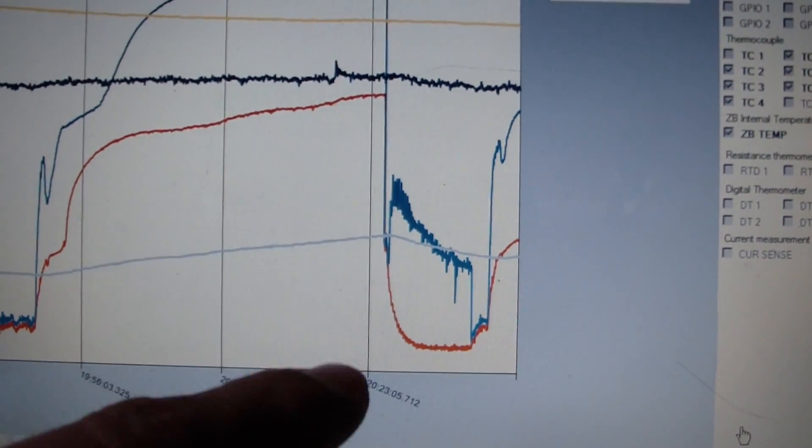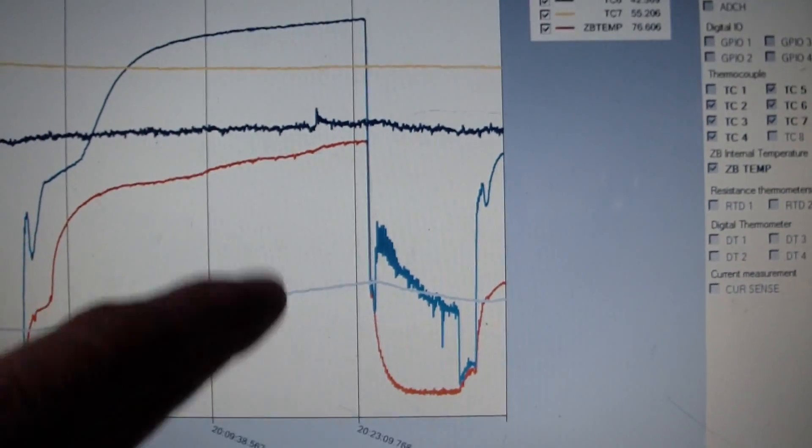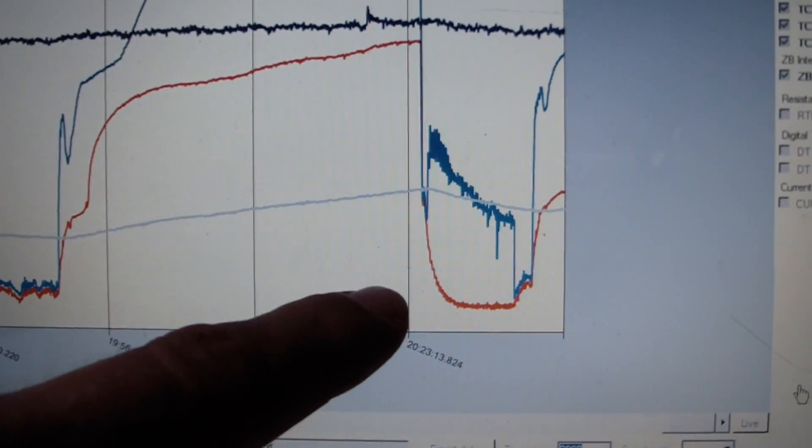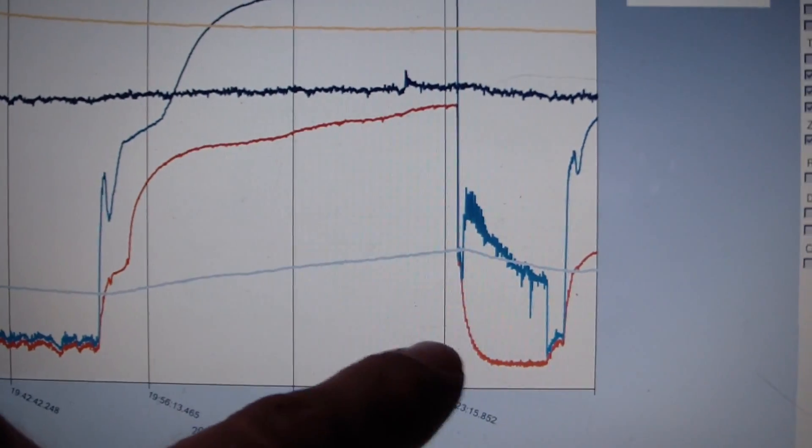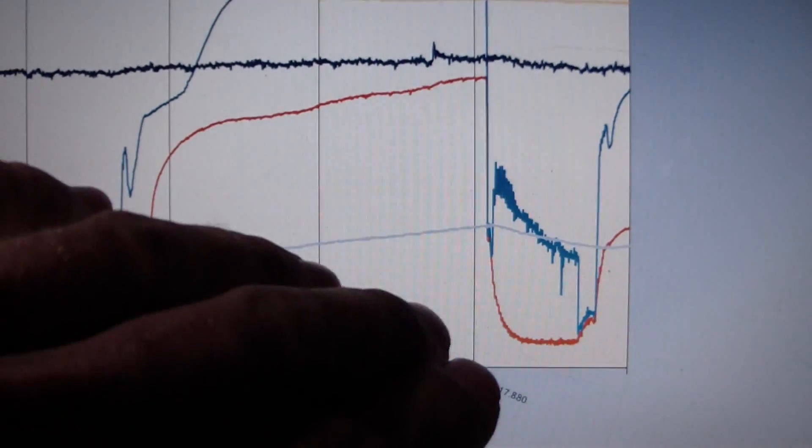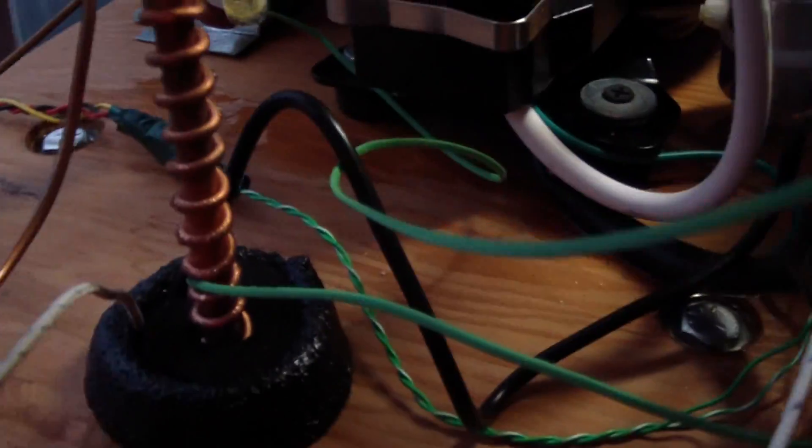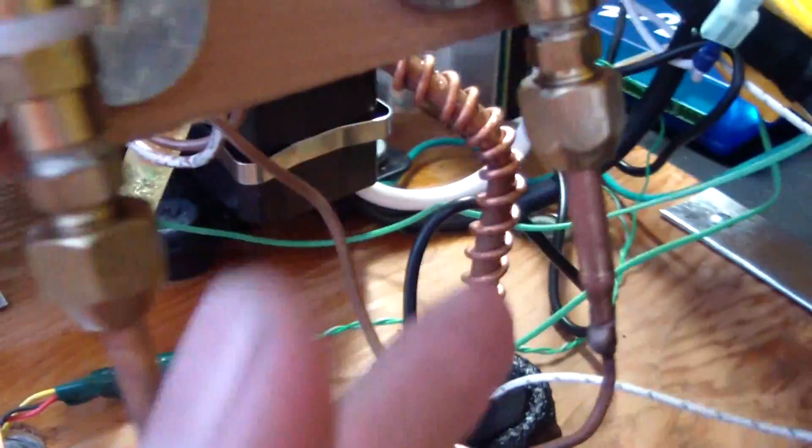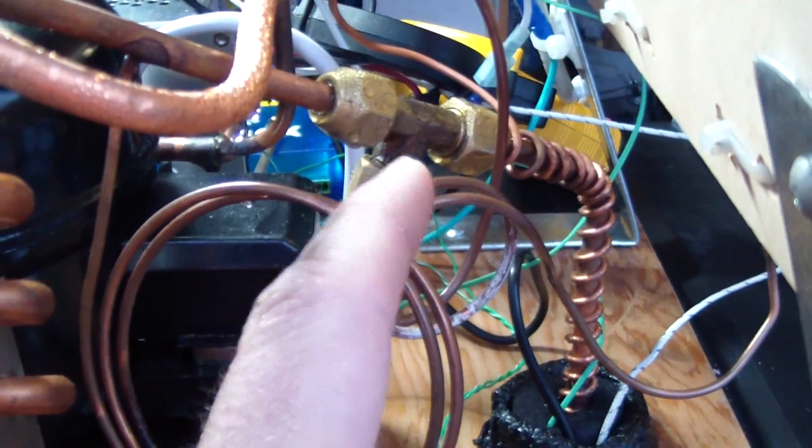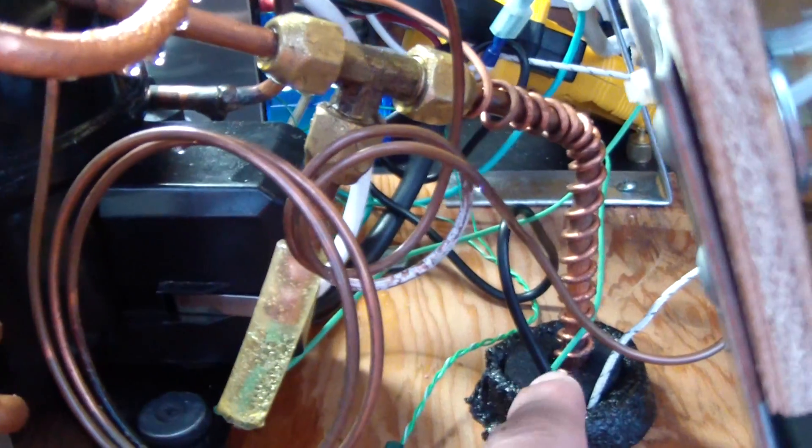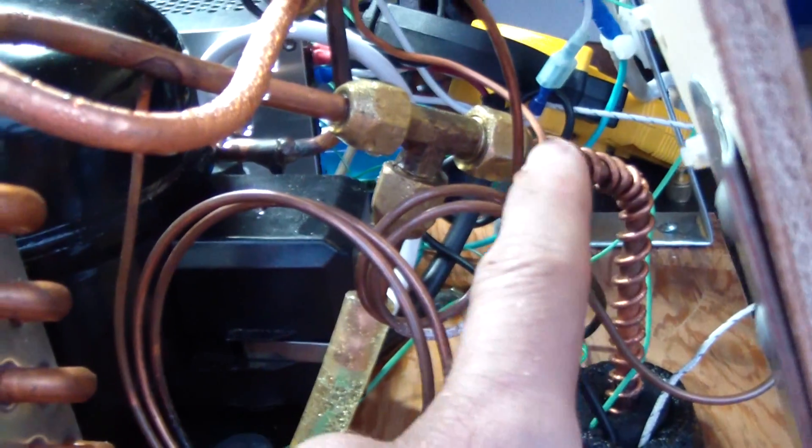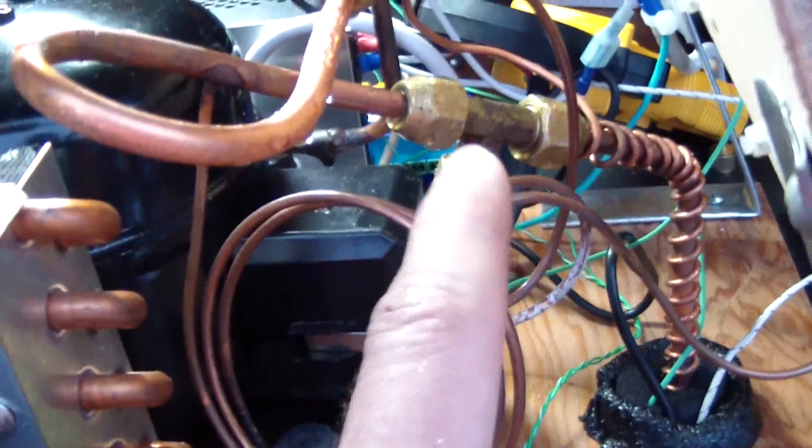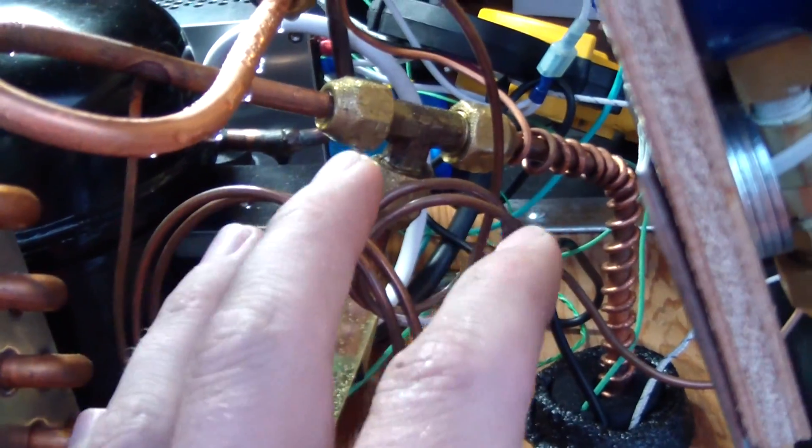But what I want to point out here is this recent run here, I don't know, eight, maybe 10 minutes at the most. You can see the sharp drop in temperature there. The red one drops down to about where pretty much that saturation temperature for the pressure I'm running at. The blue one is after the heat interchanger here, so it's going to be a bit warmer because it's being warmed by the capillary tube. If I run this thing all the way down about 5 degrees, it'll start to frost up a little bit in the suction line and then be thawed here, and then it'll start to frost again and be frosty almost the whole way back to the compressor.